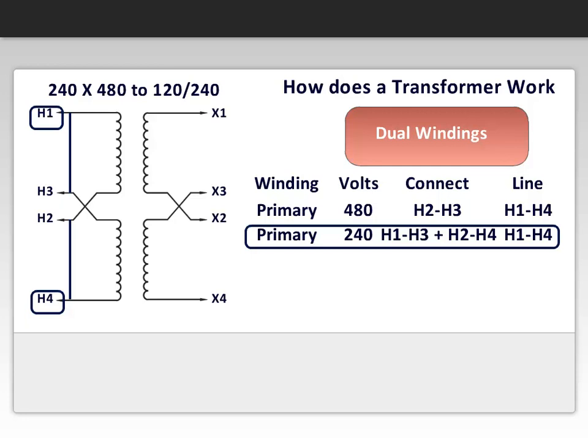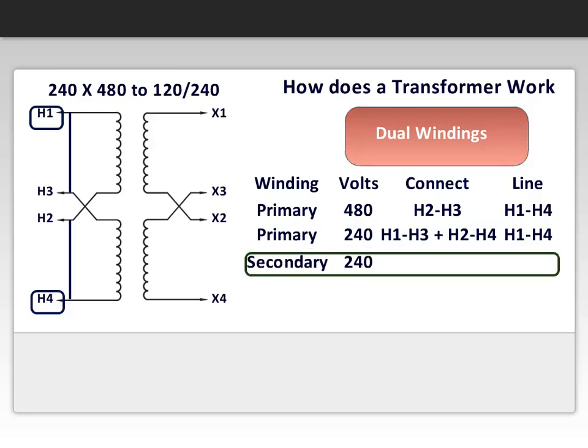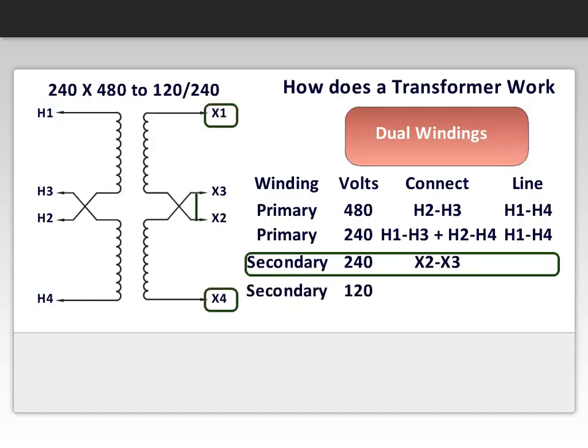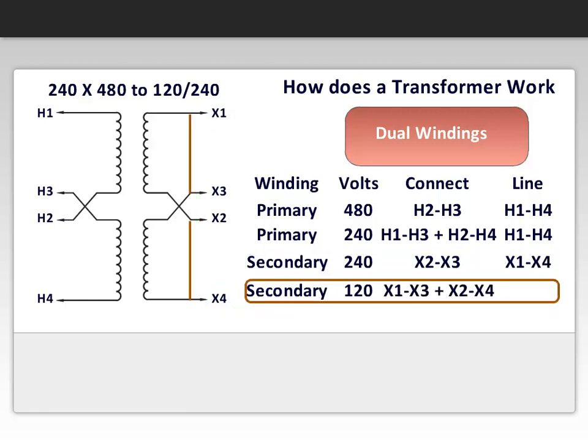On the secondary side, if 240 volts is desired, then X2 and X3 are jumpered together, while the load is connected to X1 and X4. If 120 volts is required, then X1 and X3 are jumpered, also X2 and X4 are jumpered, and the load again is connected to X1 and X4.